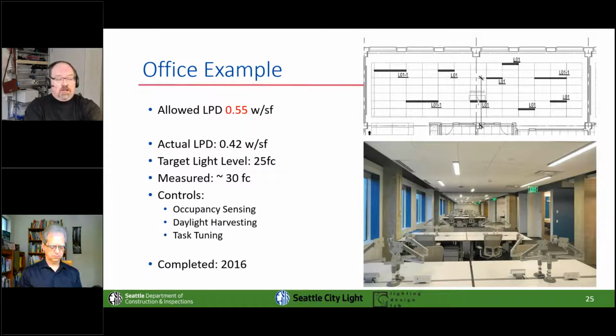Of course, it had occupancy sensing, daylight harvesting, all that good stuff. This is from 5 years ago, and our allowed watts per square foot with the new code is 0.55. The actual lighting power density there is 0.42. This is simply to show that it's certainly possible to meet and exceed the energy code as we currently have it.